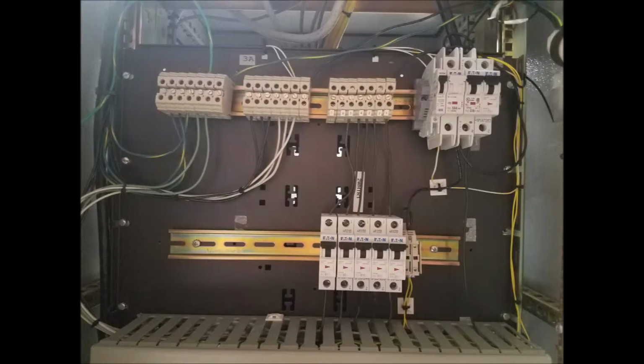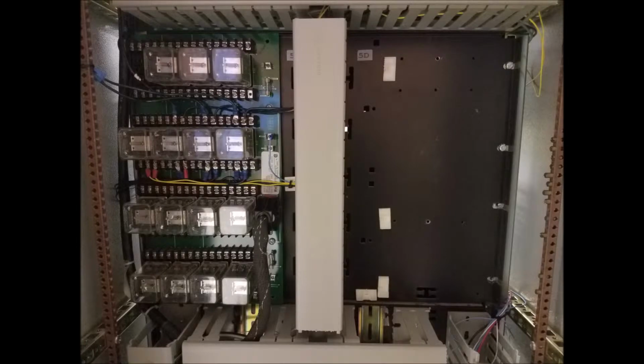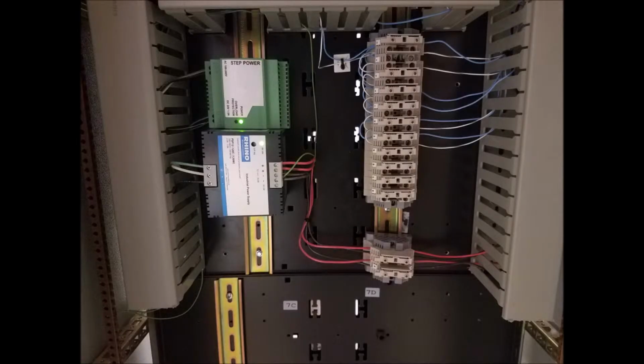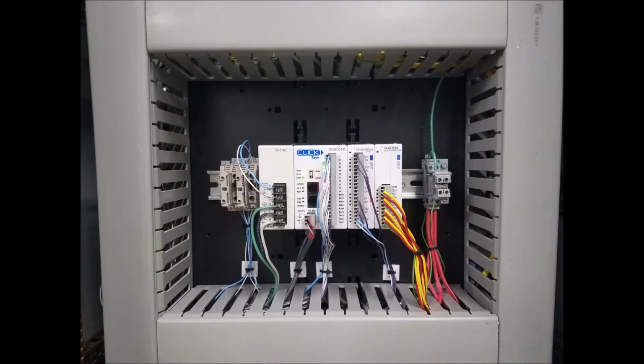On the power side, we ran all external power through breakers. We then used 4 ice cube relays for the water heater, both pumps, and the e-stop. On the very bottom, we have a 24-volt and a 12-volt DC power supply. As mentioned before, we used a Click PLC to fully automate the process. Here's an image of part of our PLC program used.